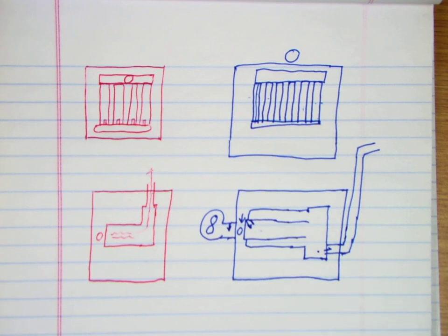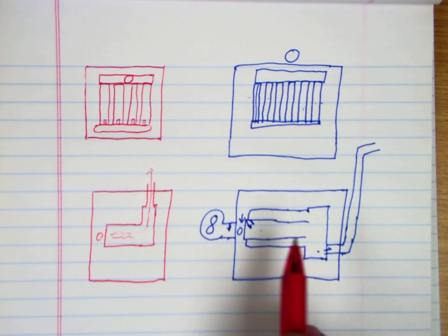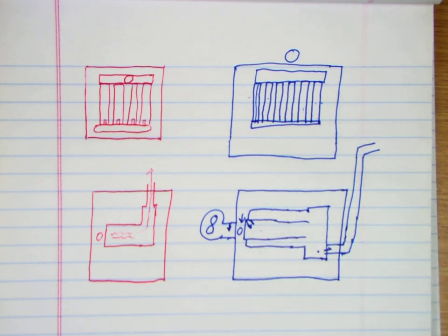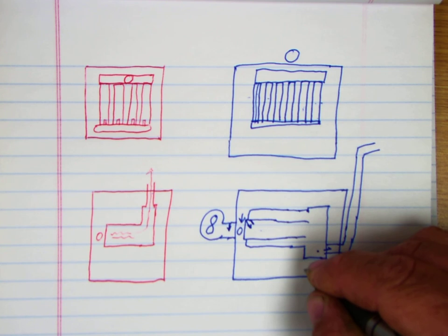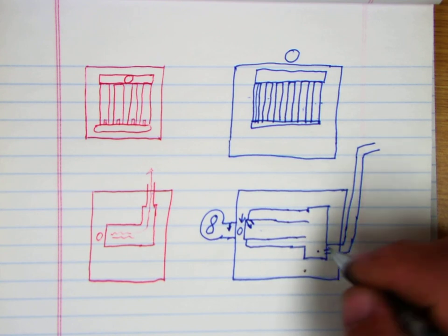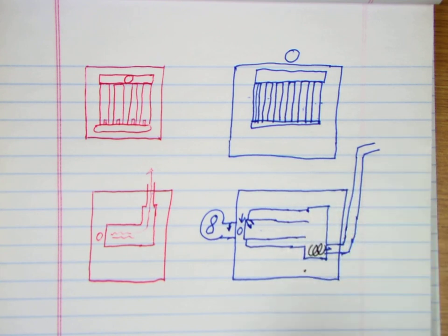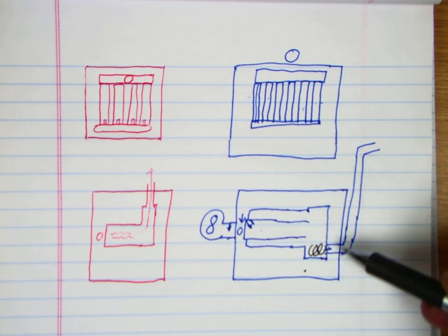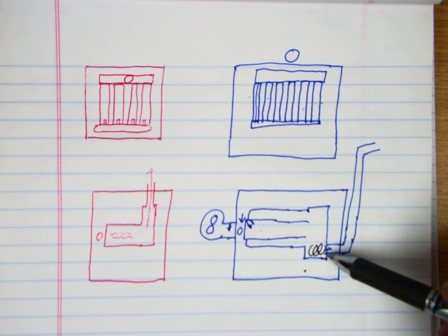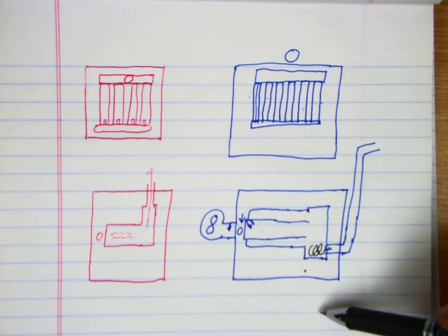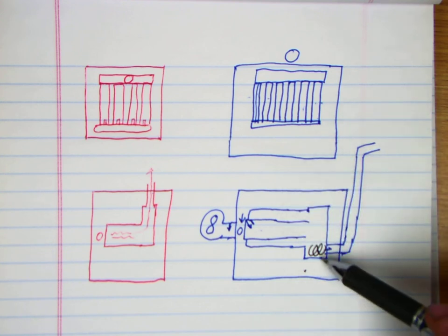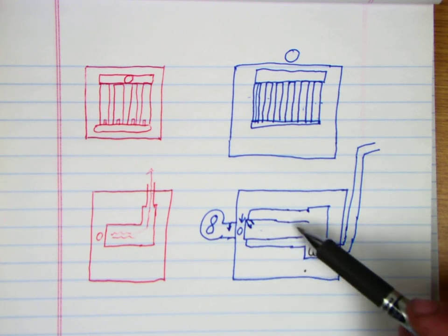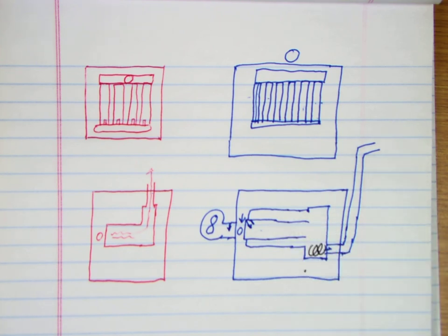Like I say, they didn't last very long because shortly after they came up with this mid-efficiency design, they went to the high efficiency, which simply added another coil in here that exhaust gas circulated through. It gave the main fan, which is blowing air across it, a little more chance to extract all the heat out of that, and that took the efficiency on those from the 80% range up to the 95, 98% range.